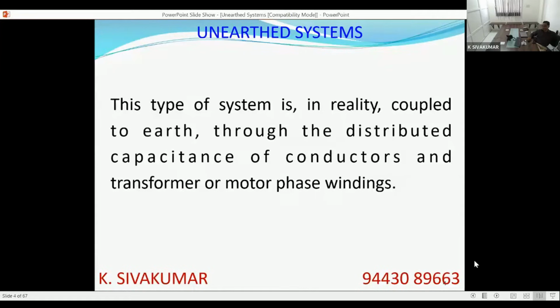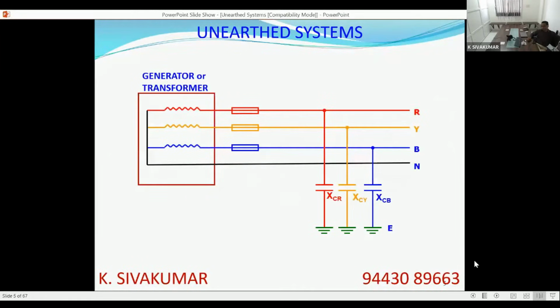There will be a capacitive coupling. Even if you take a cable, there will be a conductor and armor, and in between a dielectric. So wherever there are two conductors and a dielectric, a capacitance is formed. In fact, to be more precise, all unearthed systems are capacitively coupled earthed systems only. So it will be like this. The R phase to earth will have a capacitive reactance XCR, the Y phase to earth will have XCY, and the blue phase to earth will have XCB. This capacitance will be there in the system. Capacitive coupling will be there.